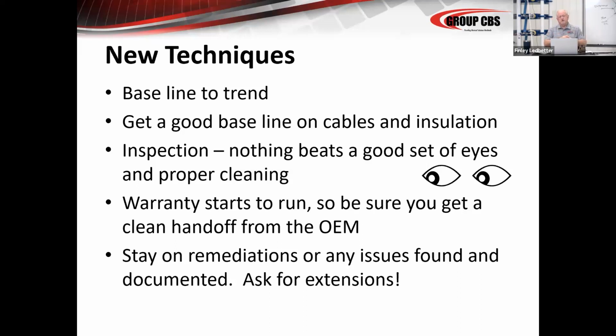So for missing things, any discrepancies you find, make sure they're noted and very carefully stay on remediations of any issues found and documented. Ask for extensions in your warranty if they cannot make that equipment 100% ready for you on the date you plan to go into service. You can ask for the warranty to stand still until they get the equipment completely assembled. If a particular item is missing, the spares aren't there, the breaker tools aren't there, wrong size fuses were shipped, connecting links aren't right, whatever. There can be thousands of problems. Don't be afraid to ask for a standstill or an extension in your warranty if by chance the manufacturer has not been able to supply you complete gear that is ready to be used and in the configuration you expected.